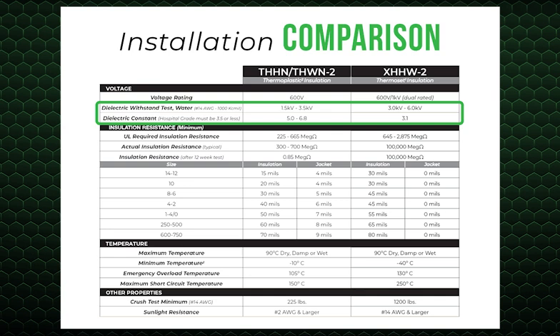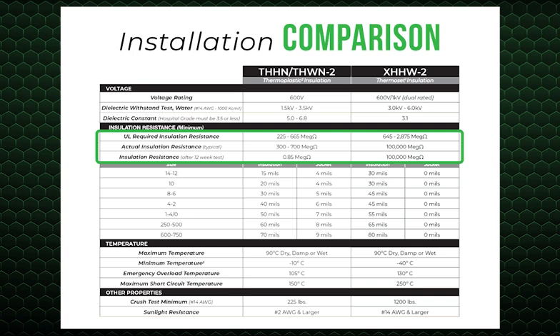Dielectric constant measures the ability of cable insulation to store electrical energy. The lower the number, the better the insulation compound. Cables must have a dielectric constant of 3.5 or less to be hospital grade. This rating is important for any application with critical circuits at risk of electrical interference from high leakage currents. Service wire's thermoset XLPE has a dielectric constant of less than 3.1, which exceeds the performance of most commercial-grade cables. XHHW-2 offers greater insulation resistance, protecting against electrical shocks and preventing equipment damage from accidental discharges.